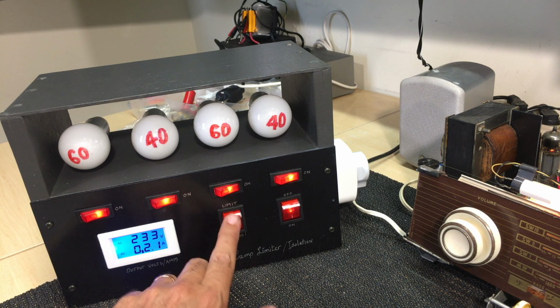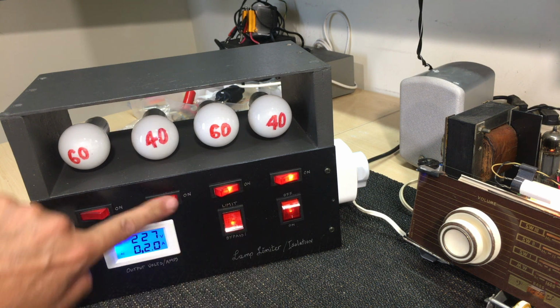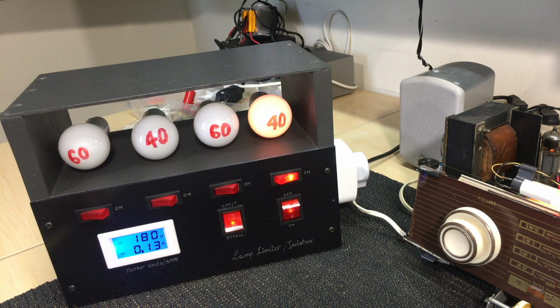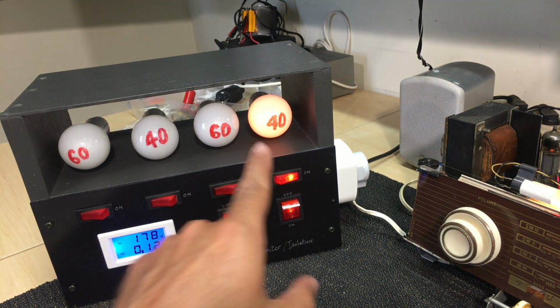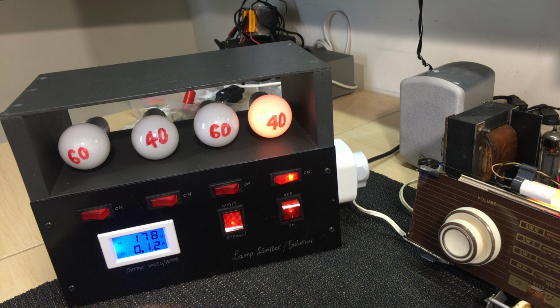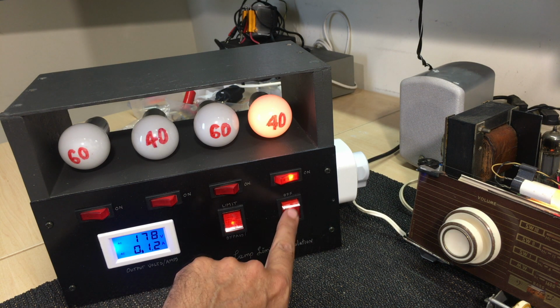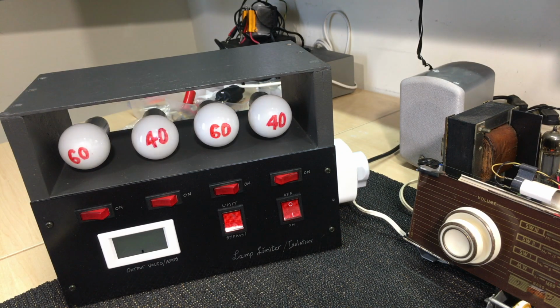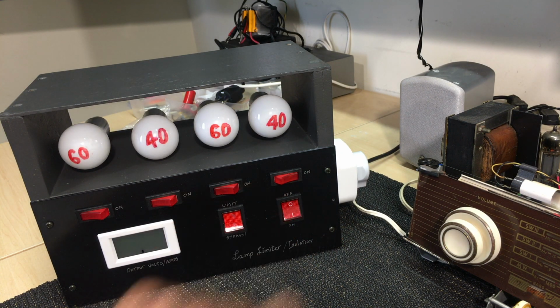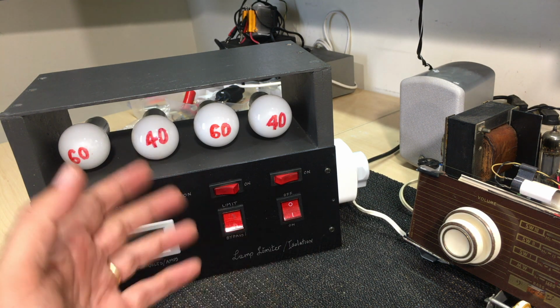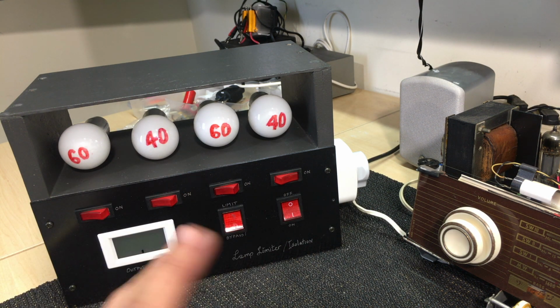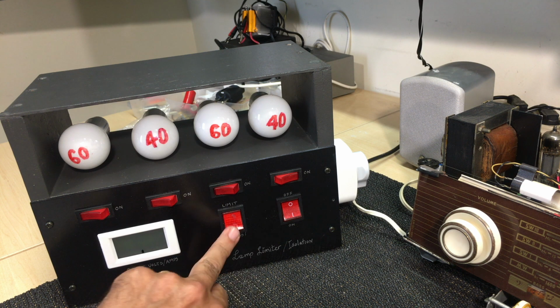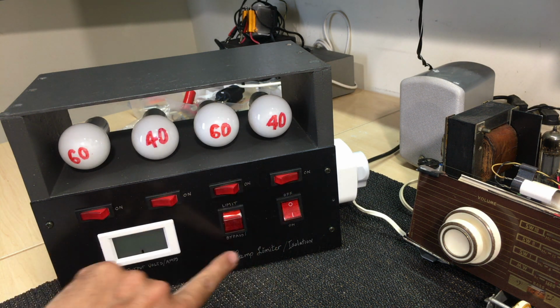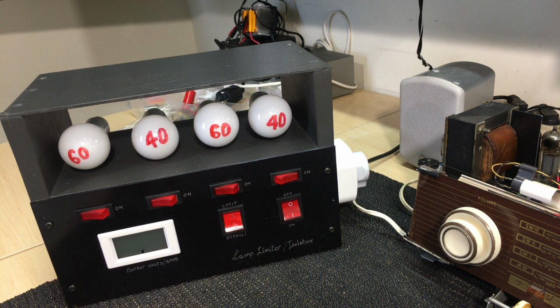So again, this is how the system works. As you can see, I brought it back down to maximum limit — in other words, minimum light bulb — and I've got 178 volts there again, and I can just switch the whole thing off. Very handy to have this available, because sometimes you see sparks and want to switch off rather quickly. One of the biggest risks is switching it on with the limit but on bypass, so you have to be very careful with this.